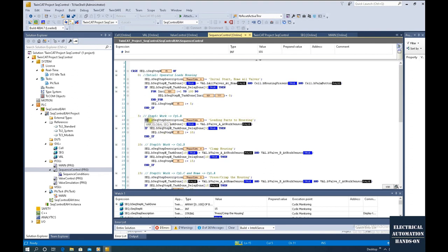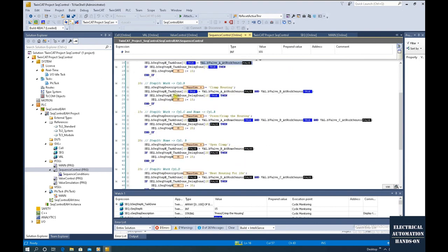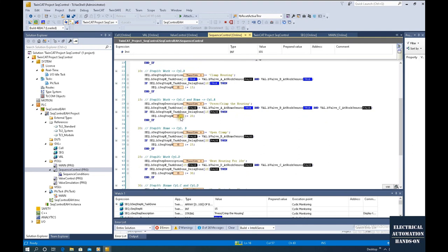Firstly, I prefer to use this string description to describe the current step and what it's doing. It's production oriented. In this comment, I note the main role of this step. And this line is the condition, using common logic, for example AND, or some complex logic combined together, to control this step moving to the next step. Using this number, we can quickly find out that currently we are stuck at 15, and find the reason that doesn't allow step 15 to move forward, right?